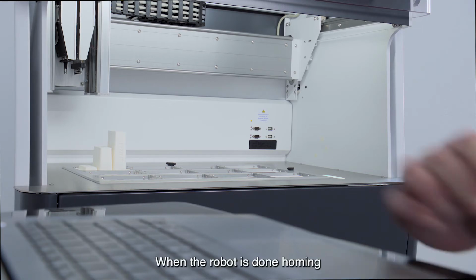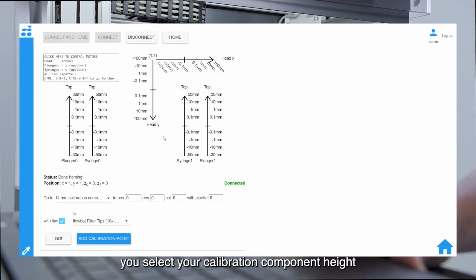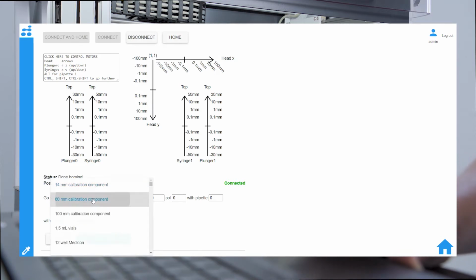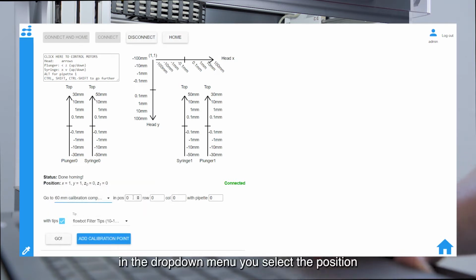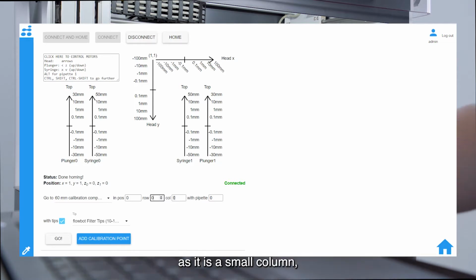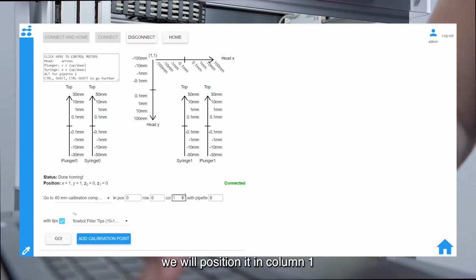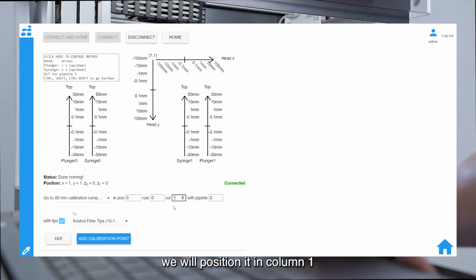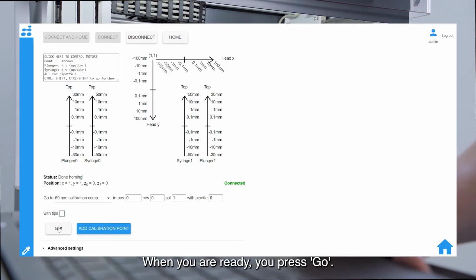When the robot is done homing, you select your calibration component height. In the drop-down menu, you select the position, and remember in liquid level control, you start off the count with 0. So the top left corner is position 0. We will be placing it in row 0, and in this case, as it is a small column, we will position it in column 1. We will use the left pipette, so that's pipette 0, and we'll do it without tips. When you're ready, you press go.